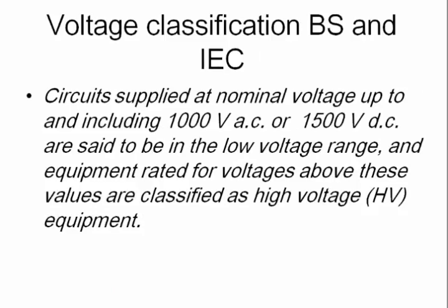So voltage classification based on British standard and IEC, which is also used in Australia and most other European countries. What's the classification of low voltage? Low voltage is anything under 1000 volts AC or 1500 volt DC. Anything over, technically or safety wise, is considered high voltage. Anything over 1000 volts AC and 1500 volt DC is said to be HV for safety. However, there is a difference which is not a standard based difference in industrial terminology.